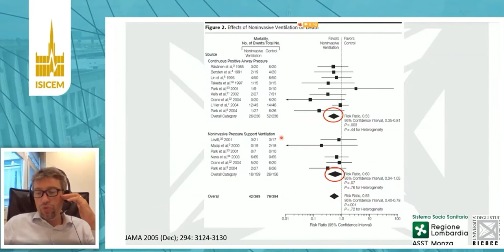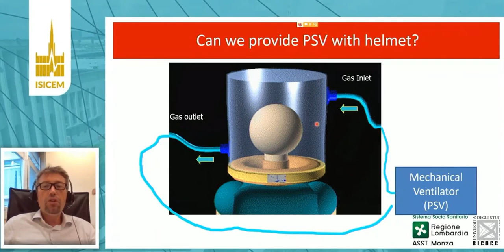connect our helmet with a mechanical ventilator, sorry, which should be set in pressure support ventilation mode. I would discourage you to connect the helmet to a ventilator set in CPAP mode, and I will explain you why. Now, this is, in my opinion, not the best way to use the helmets, because if you really want to deliver pressure support ventilation, if you want to assist the ventilation of the patient, you need something which is fast. You need a fast ventilator, but you also need a fast responding system.